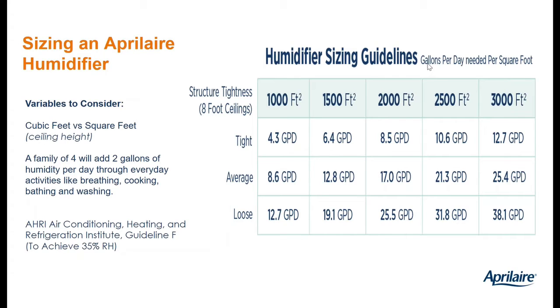So let's go back to our example. 2,000 square feet, assuming 8-foot ceilings. Whenever you see a chart like this, AHRI uses square feet, and they always assume 8-foot ceilings. So you could calculate the cubic feet if you had 10-foot ceilings or 12-foot ceilings or cathedral ceilings and just use the same table, but use cubic feet instead of square feet and ceiling height. So 2,000 square feet, 8-foot ceilings, half an air change per hour is tight. You can see the calculations right there. Same thing, same idea.